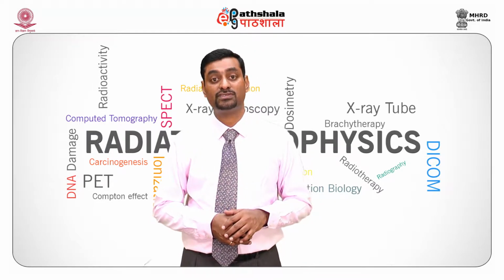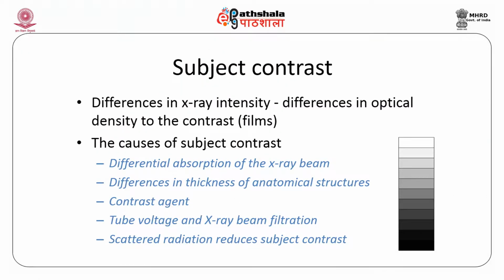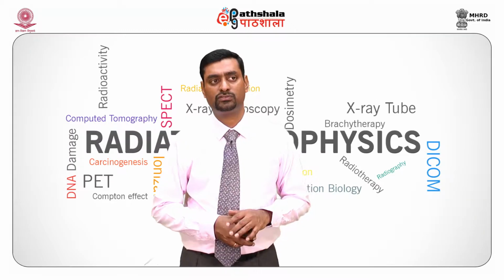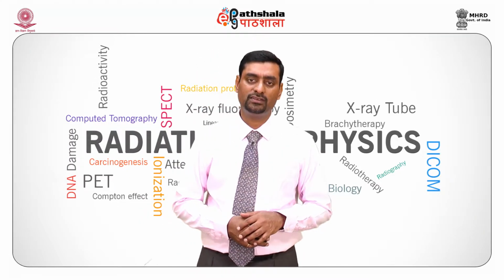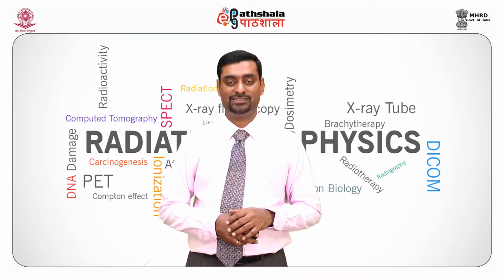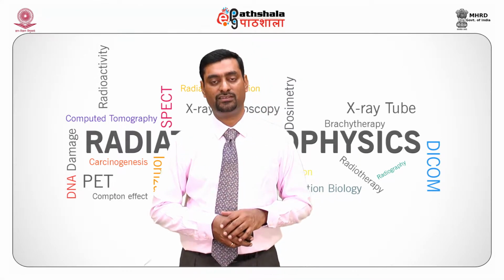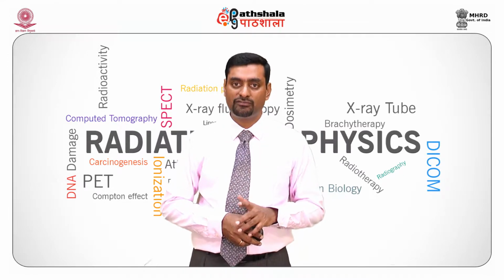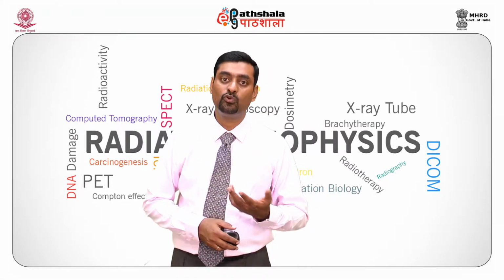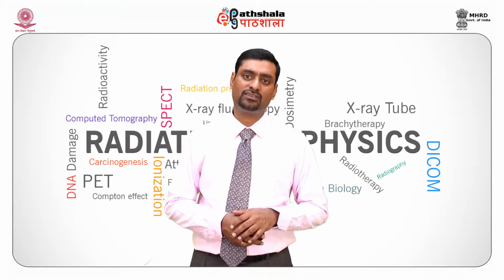What are the causes of subject contrast? Differential absorption of the X-ray beam, differences in thickness of anatomical structures, use of contrast agent, tube voltage and X-ray beam filtration. Scatter radiation also reduces subject contrast. So scatter radiation, how do I overcome that? By using grids. The function of a grid is to cut off the scatter from the subject and improve image contrast. There is also detector contrast.